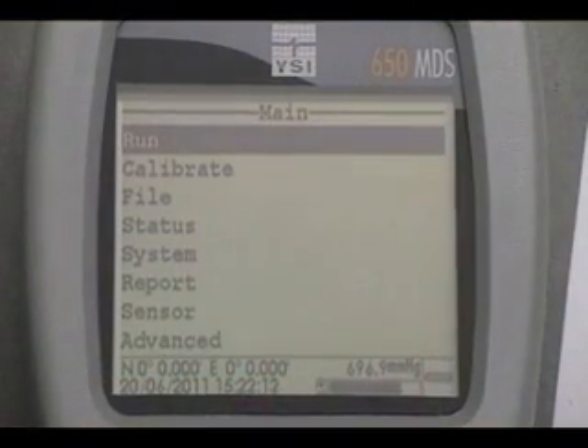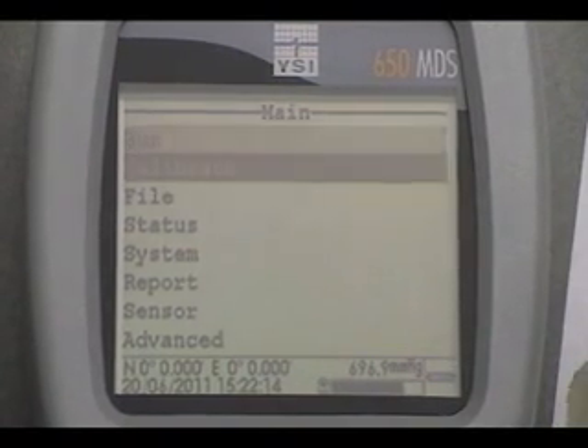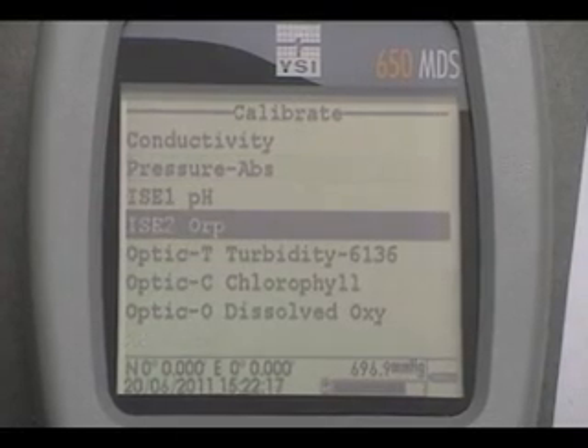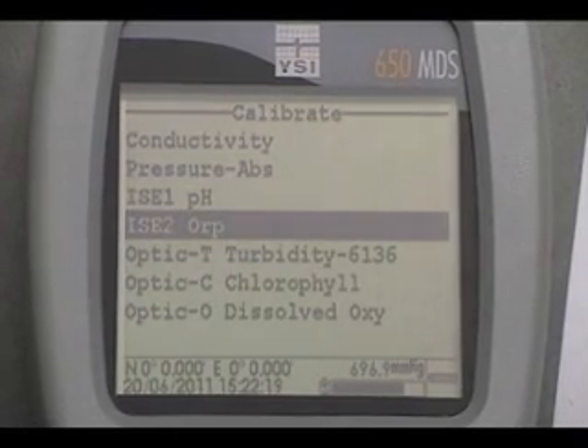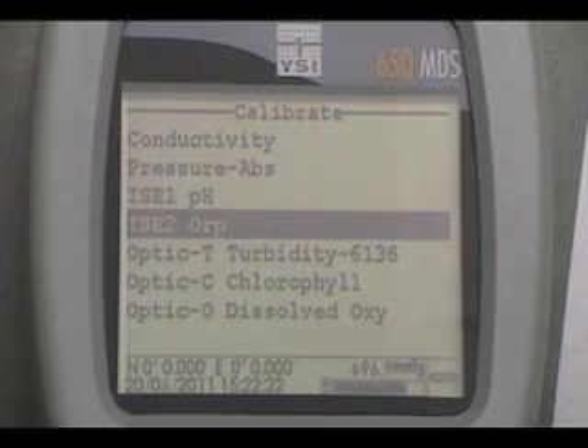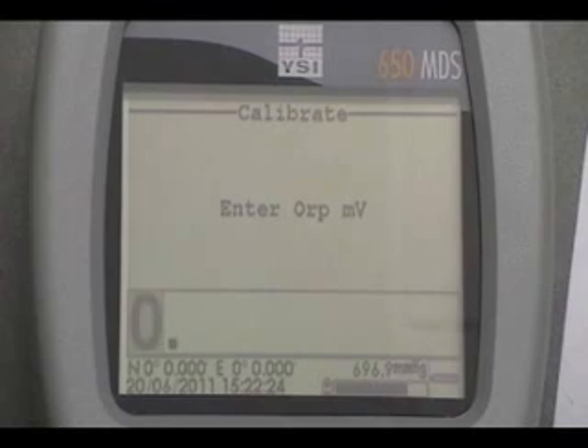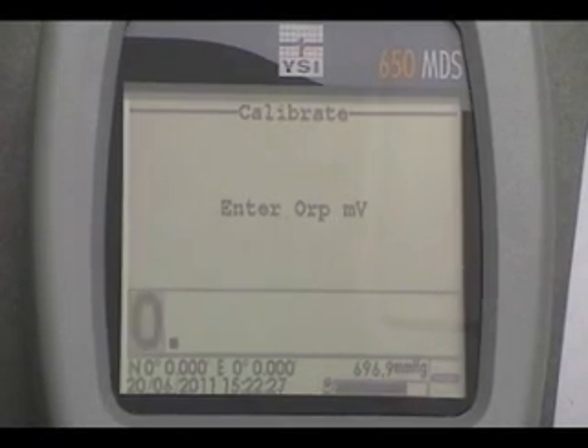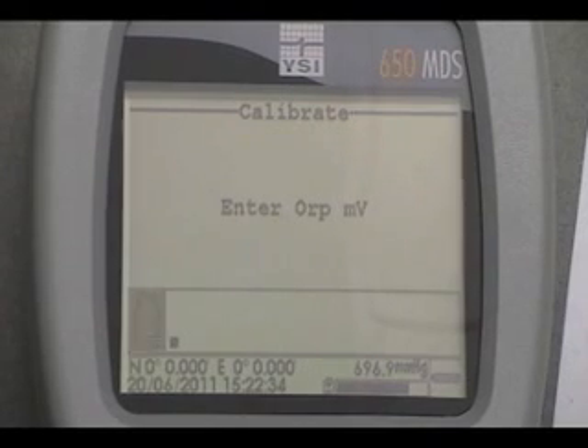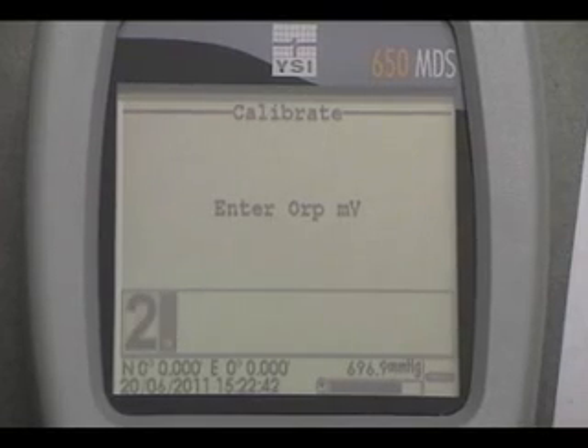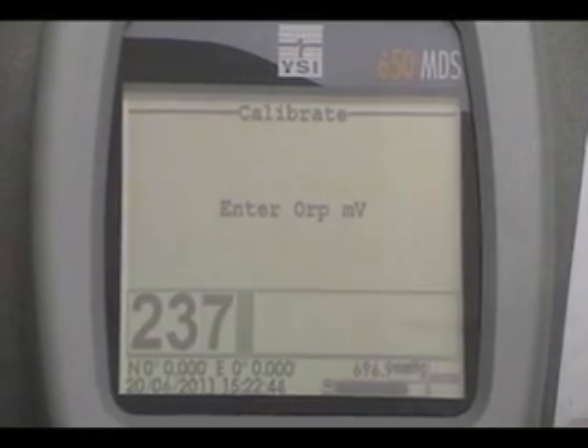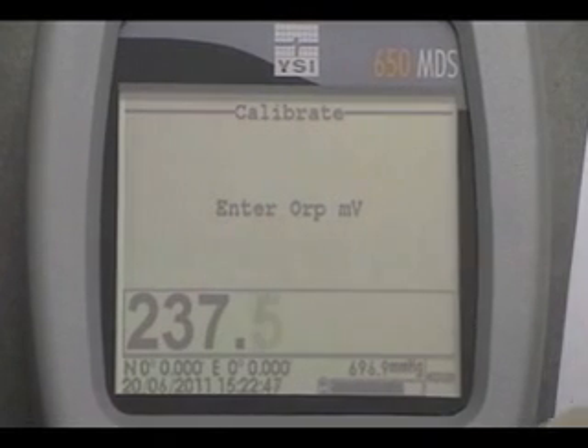Step 4. From the sonde menu, select Calibrate and press Enter. Step 5. Select ISE2 ORP and press Enter. Step 6. Enter the value of the ORP solution in millivolts at the calibration temperature. See the table in the instruction manual. For example, if we are calibrating at 20 degrees C, the value to enter will be 237.5 millivolts. And press Enter.